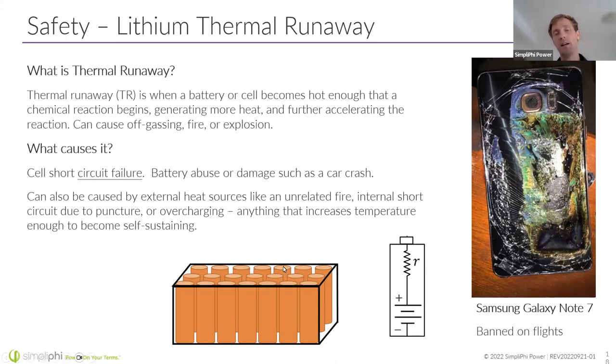NMC batteries, LCO batteries, these batteries that contain cobalt are slightly higher voltages and burn much more quickly. With the case of our battery cells, we use LFP cells and they essentially put themselves out. You can see our fire tests in which UL actually forces a cell into thermal runaway, makes that cell off gas, but the battery does not propagate chain to chain, cell to cell in a chain reaction fashion, right? The battery puts itself out.